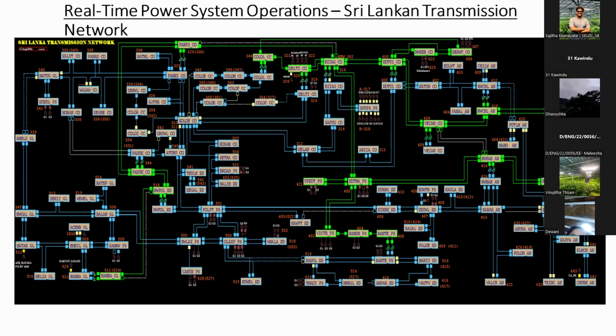Can someone tell me how they connect it? By using interbus transformers, right? Using interbus transformers, they can connect the 220 and 132 networks. These interbus transformers are very important, because they act as the point where generation pumped into the 220 network comes down to the 132 network. There's no one consuming active power directly in the 220 network; all consumers are connected to the 132 network or at 33 kilovolts. So whatever generation is pumped into the 220 network must come down to the 132 network.